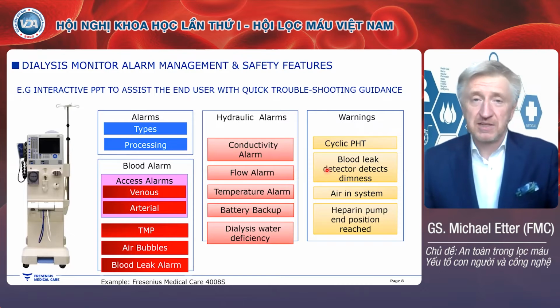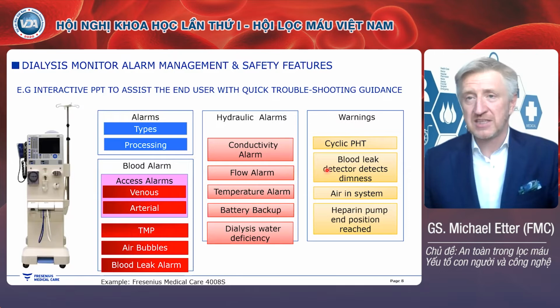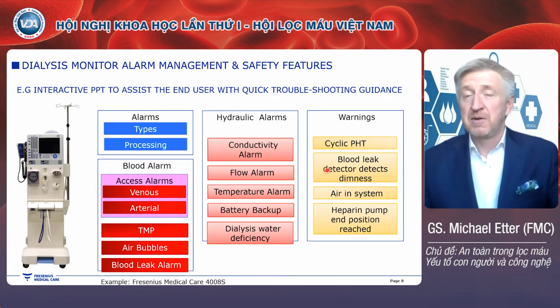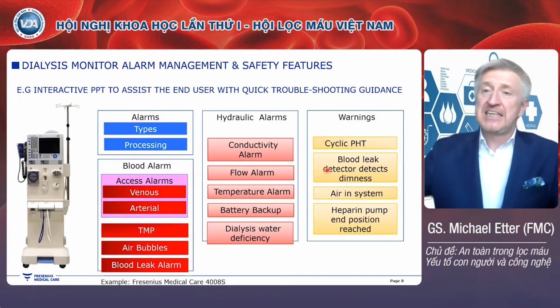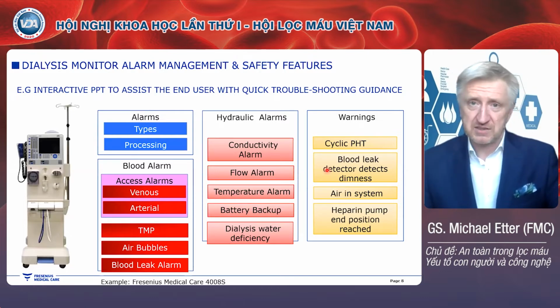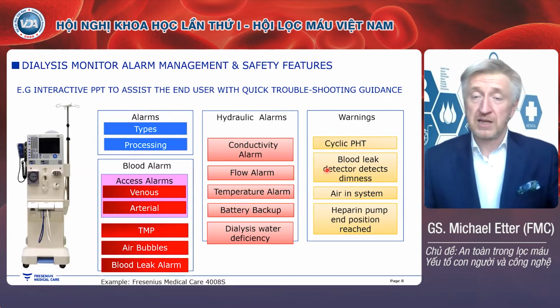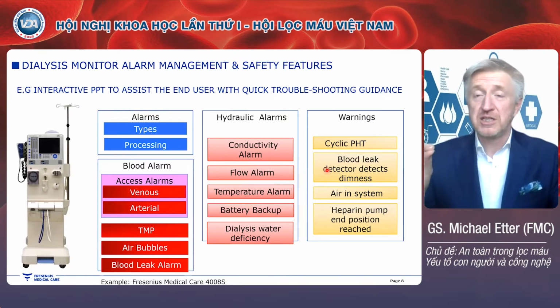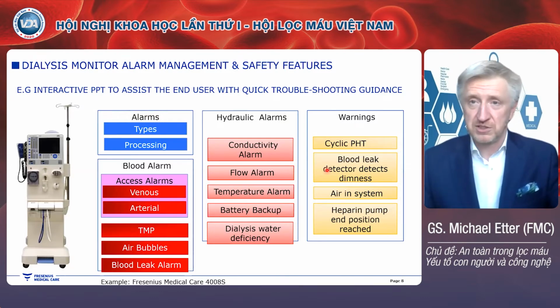There's another set of alarms, which are the hydraulic alarms. The hydraulic alarms are the alarms on the side where the dialysis fluid, or in hemodiafiltration, the substitution fluid is processed. They are very different from the alarms on the blood side. They may not be as critical, but they are still very important to steer the treatment, to control the treatment in the most efficient way.